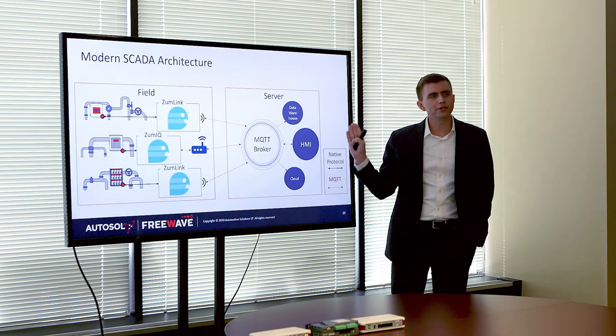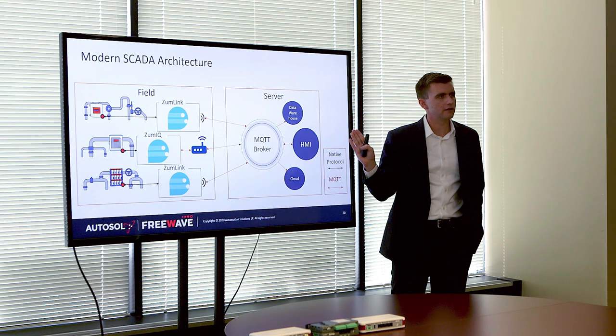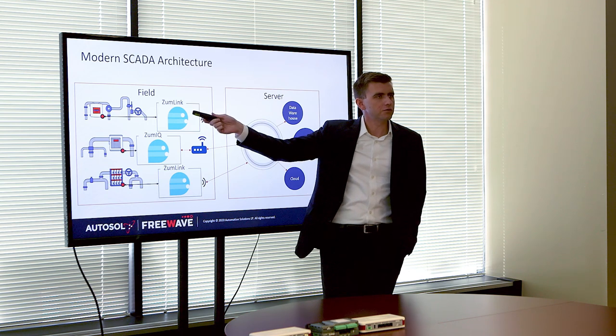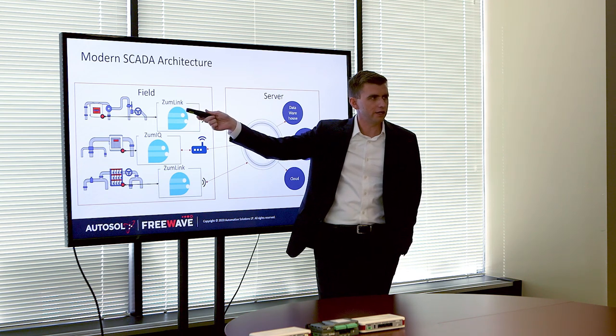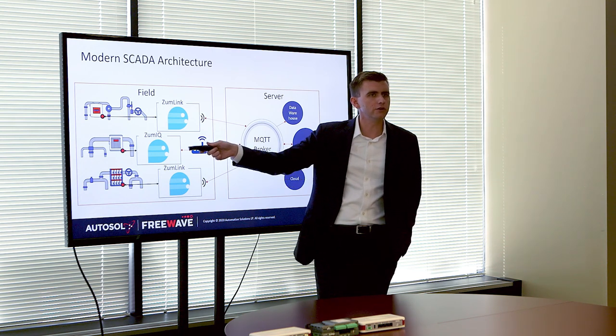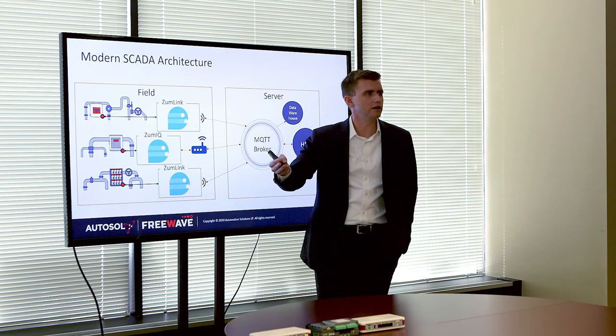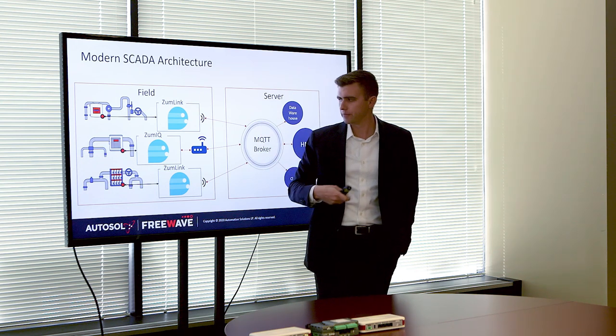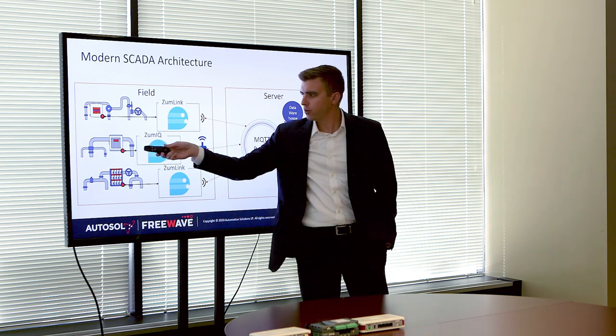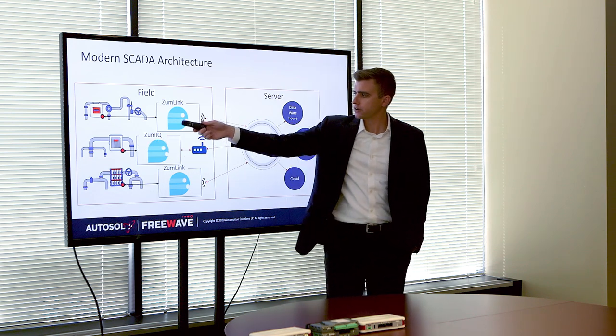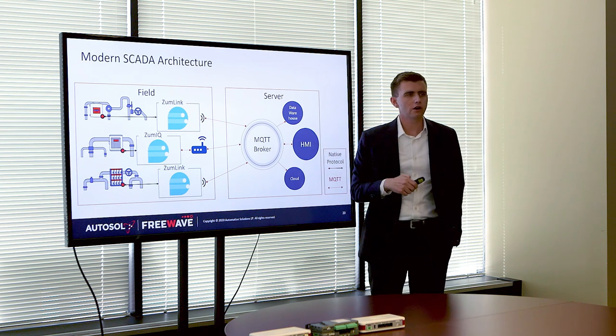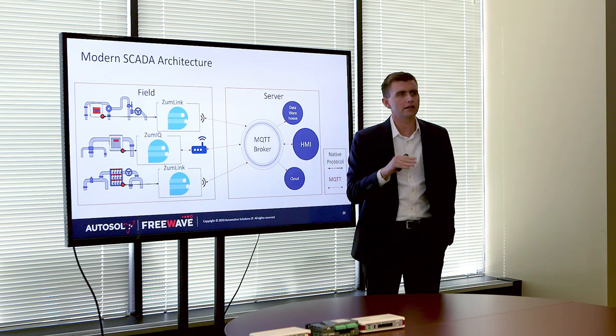Here is how an MQTT data network would look. You have your end devices, and you could replace your existing communications with something like a ZumLink radio with Edge ACM. Or you can keep your existing communication and use the ZumIQ — an industrialized switch that can run Edge software like Edge ACM — and just put it behind that existing radio or cell modem. You still poll the end device in native protocol, convert to MQTT here, and send it up to a broker where multiple pieces of software can subscribe to the data they want.